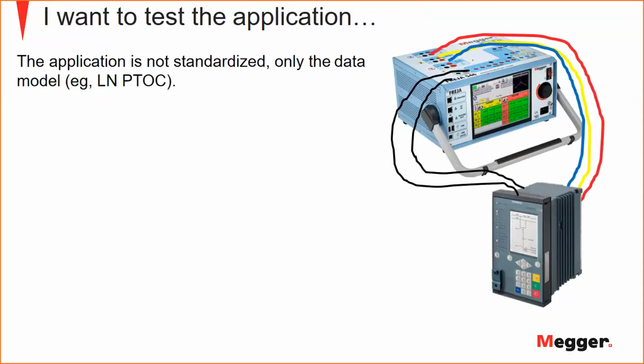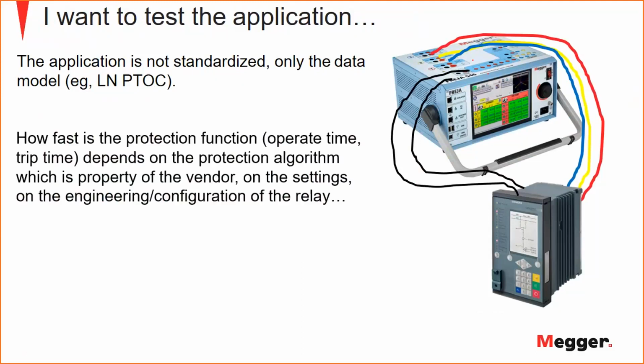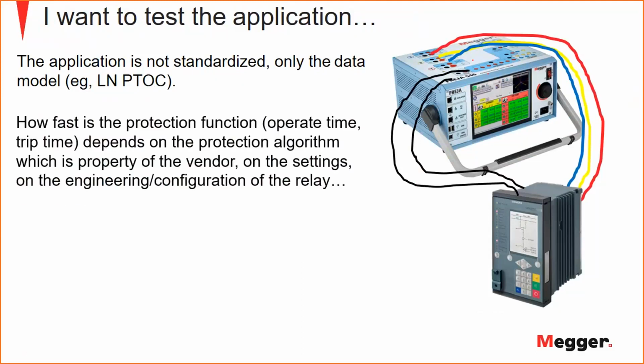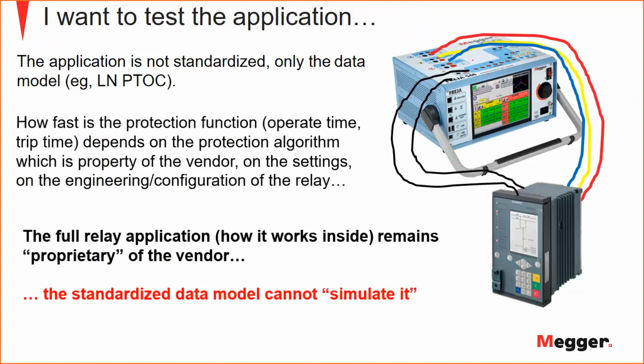Why? Because the application is not standardized. The data model is standardized, but not the application. So how fast the protection function trips depends on the algorithm. Protection depends also on the relay settings, and on the engineering and the configuration of the protection relay. The real application, the relay application, and how it works is proprietary to the vendor, and it will remain proprietary to the vendor. It's not standardized. We have only standardized the data model. So we have a gap that we have to fill.